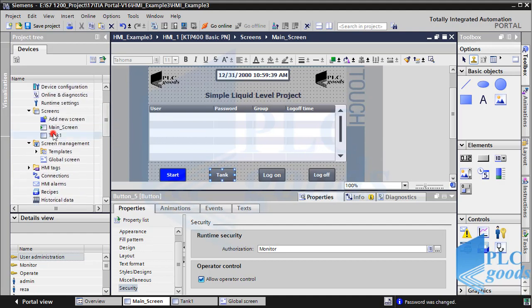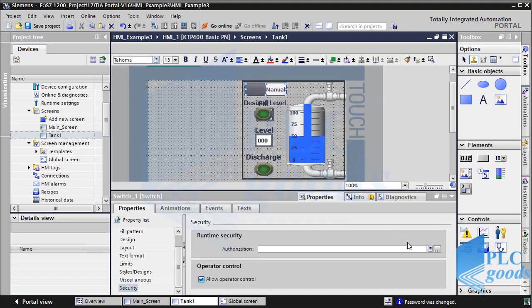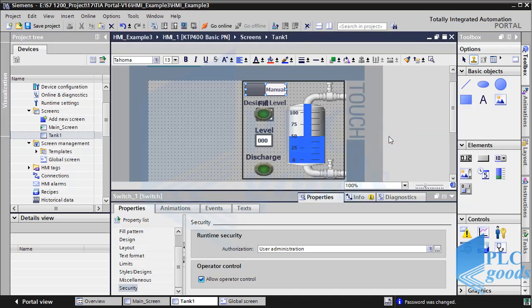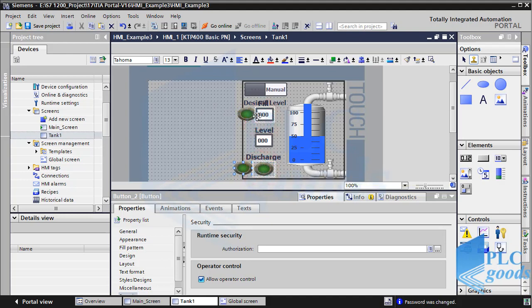Let's go to the tank screen. Suppose just the admin user can switch between auto and manual control. So in its security part I select user administration — if you remember, only the admin group has this authorization. I select operate authorization in the security parts of the fill and discharge buttons.